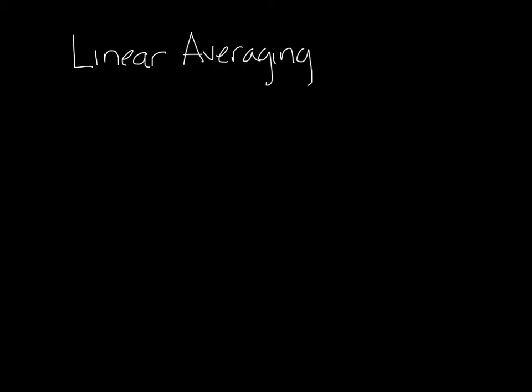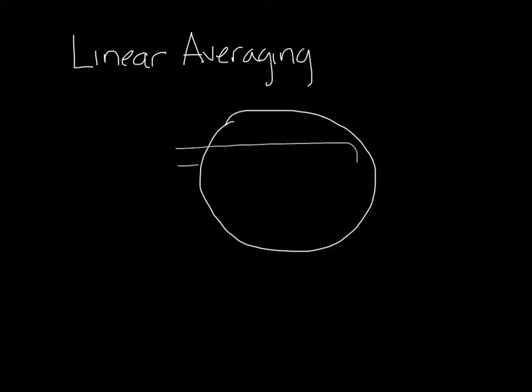At its most basic, the linear averaging sensor is in fact linear. It usually looks something like this. Let's draw the inlet to a VAV box. Now you've got a sensor here, and it's basically a pitot tube, remember, so it's an open tube with holes in it. The top one would have holes right here, and the bottom one would have holes on the back side that you can't see in the drawing.